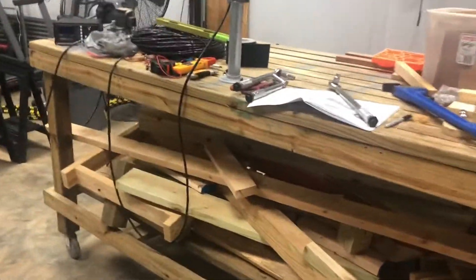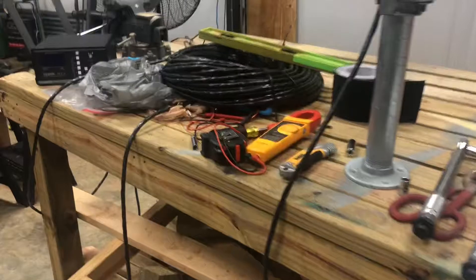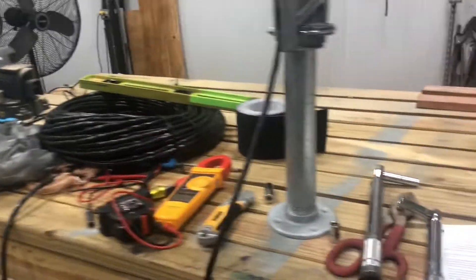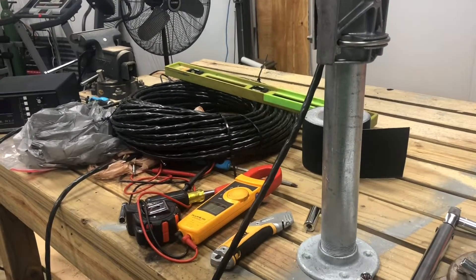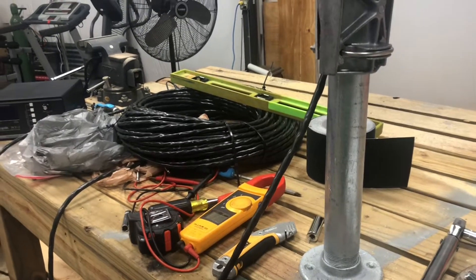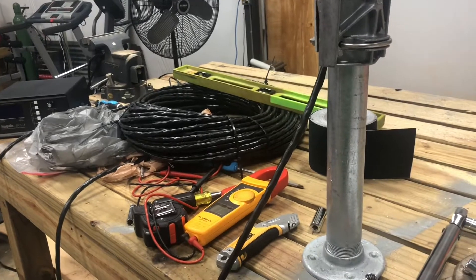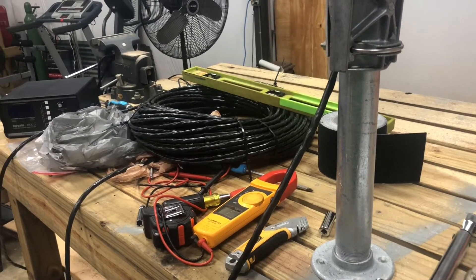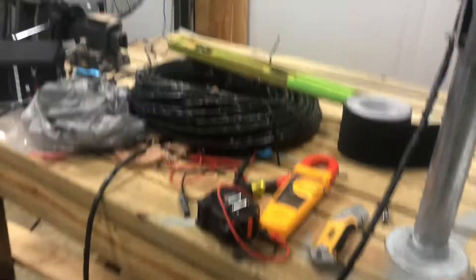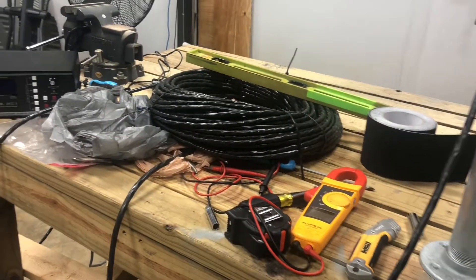Some lessons learned. So this is 240 feet of cable. They sent me six number 18s with two number 16s — eight cables altogether. They actually should have sent me six number 16s and two number 14s, but because it's over 200 feet you should go up a gauge.